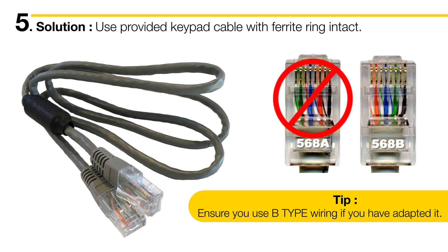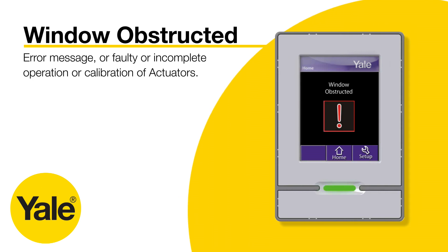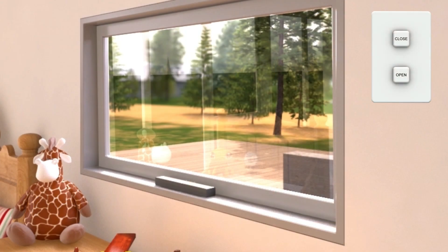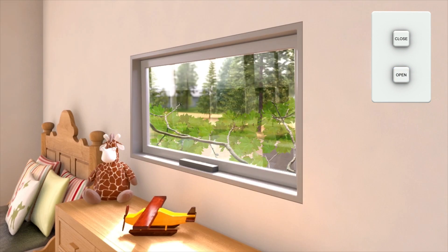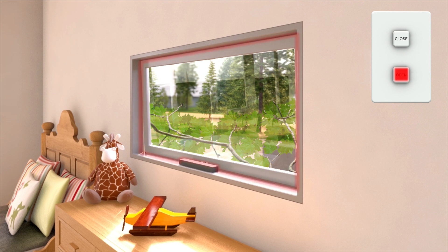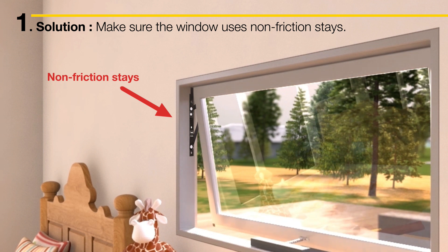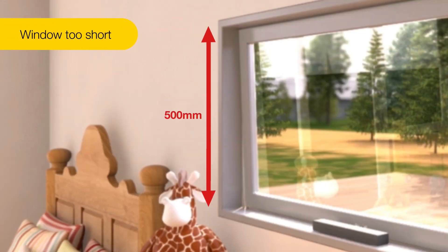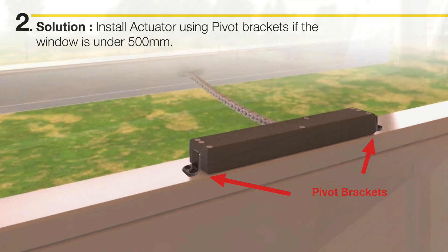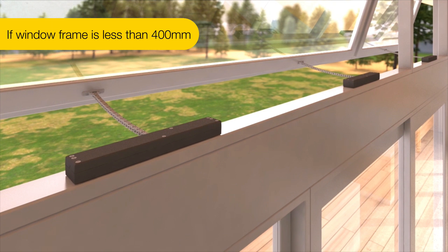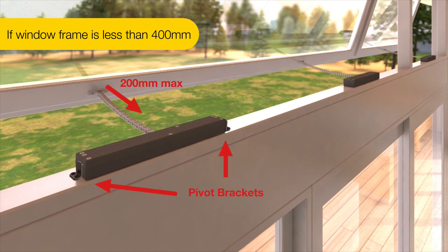Now that we've covered common communication error causes, we'll move on to what can cause a window obstructed error to appear on the keypad. Or, if you're using a wall switch or smart home system instead of a keypad, you may find the actuators start to move but stop short of full stroke and won't complete the initial calibration sequence. This error means the motor is struggling to open or close the window. Check for obstructions first, and check the windows are using non-friction stays. It could also be that the window is too short for the chain stroke. If the window sash is shorter than 500 millimetres, the actuator must be installed using the pivot brackets. If the window sash is shorter than 400 millimetres, you must use the pivot brackets and also restrict the stroke of the chain to 200 millimetres.